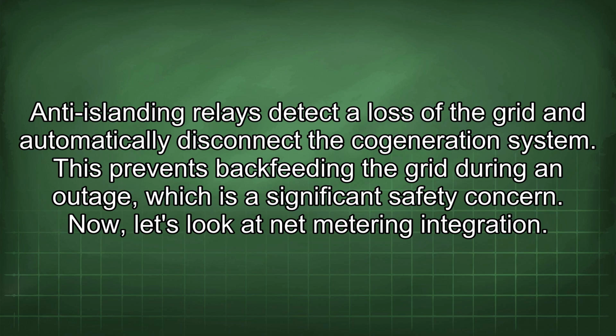Anti-islanding relays detect a loss of the grid and automatically disconnect the cogeneration system. This prevents backfeeding the grid during an outage, which is a significant safety concern. Now let's look at net metering integration.